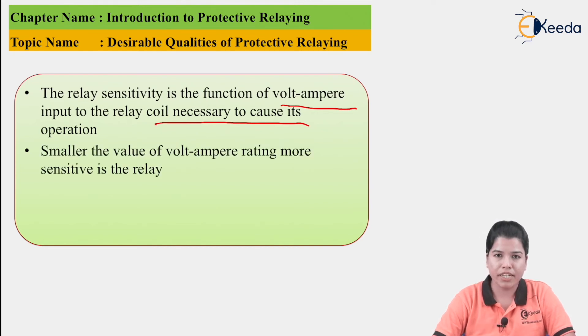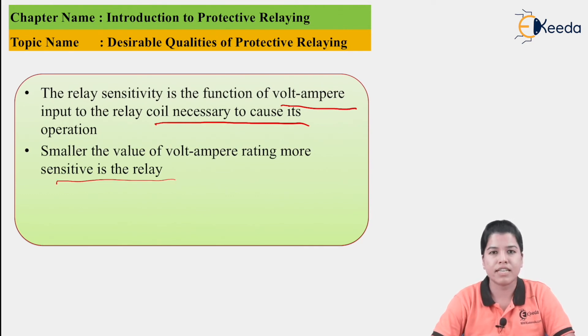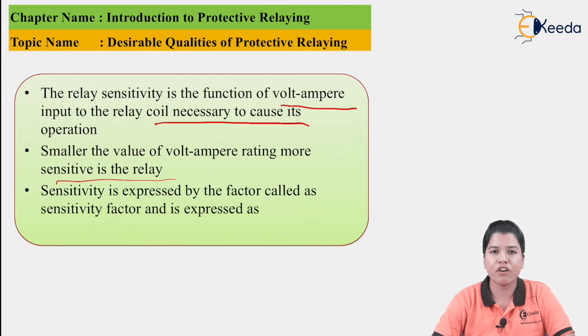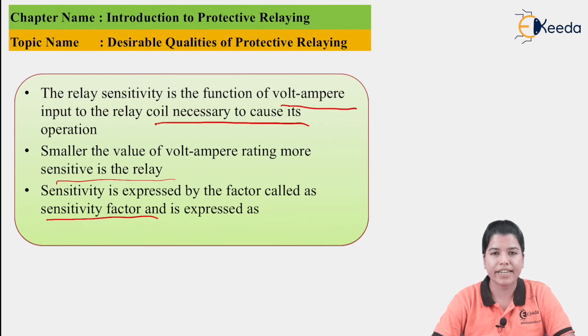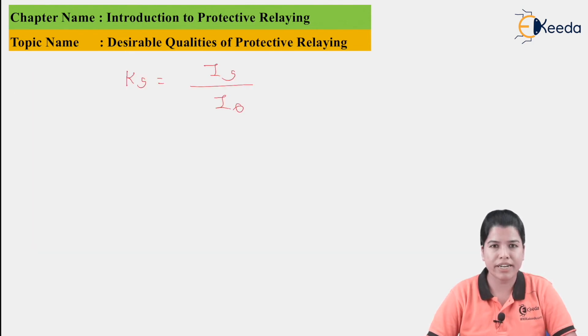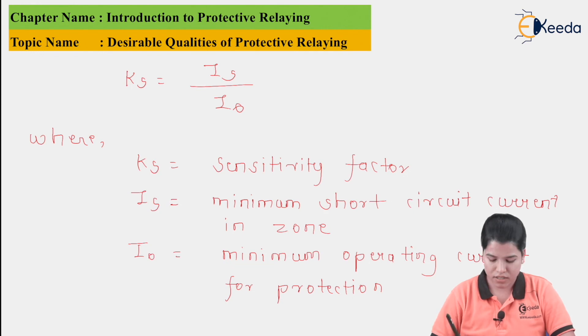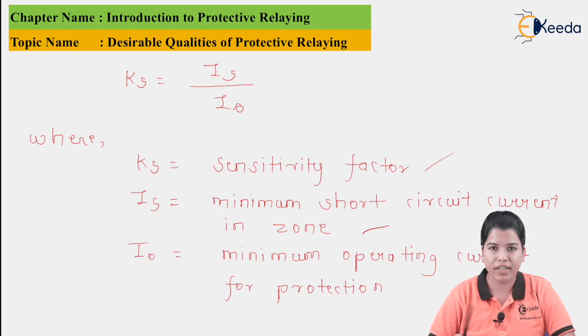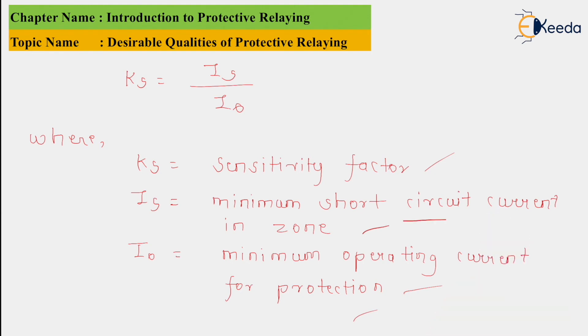The smaller the value of volt-ampere input, the higher the sensitivity of the relay. The sensitivity of a relay is expressed by the sensitivity factor KS = IS / I0, where IS is the minimum short-circuit current in the zone and I0 is the minimum operating current for protection. The ratio of IS to I0 is called the sensitivity factor, denoted as KS (or AS).